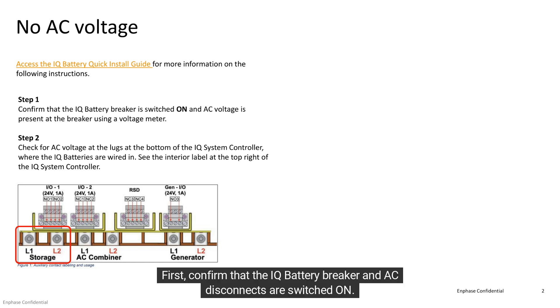First, confirm that the IQ Battery Breaker and AC Disconnects are switched on. Use your voltmeter to check for AC voltage at the breaker and AC disconnects.